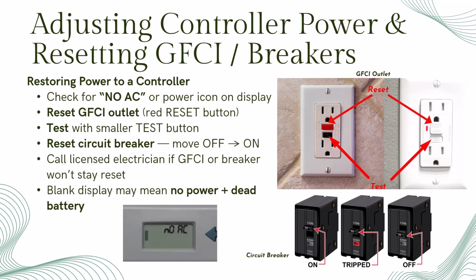One last tip: if the display is completely blank, you might have two problems: no power from the outlet and a dead backup battery. In that case, verify input voltage and transformer output before assuming the controller is damaged.